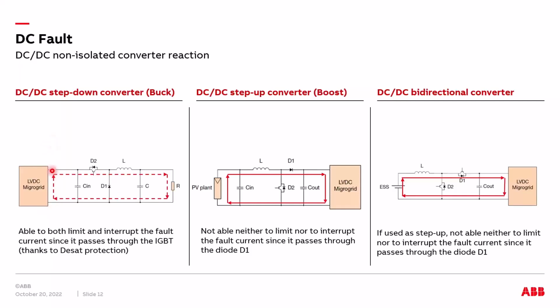But if we have a fault on our microgrid, the battery is able to supply this fault, since the current contribution is passing through the diode and we are not able to limit this contribution. The same thing if we have, for example, a so-called step-up converter or boost converter. So the voltage on the output of the converter is higher than the voltage of the input. So imagine here the input is, for example, the PV plant or the battery of our system, and the output is a microgrid. If you have a fault on the microgrid, we cannot limit this current because the current is passing through the diode D1.